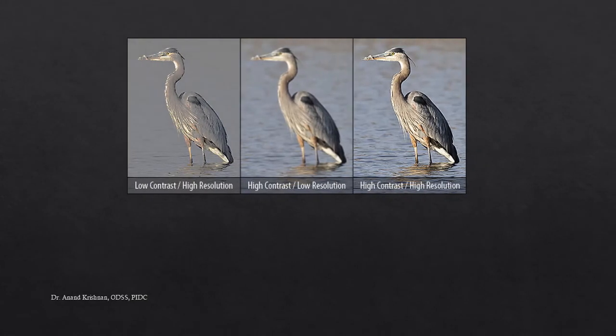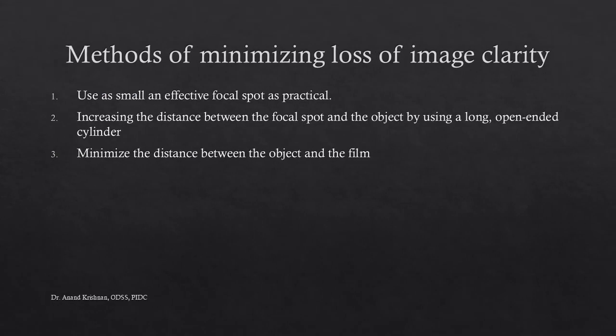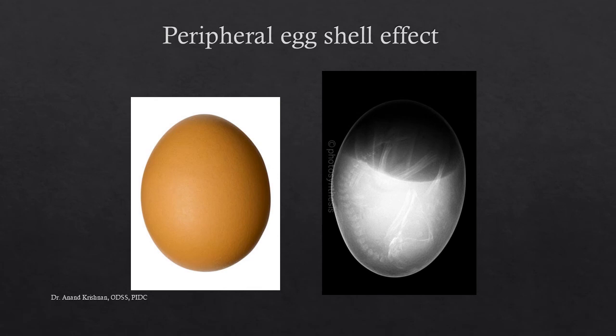To achieve good image quality, contrast and resolution must be balanced — high contrast with low resolution or high resolution with low contrast are not ideal. Methods to minimize loss of image clarity include using the smallest effective focal spot practical, increasing the distance between the focal spot and the object using a long open-ended cylinder, and minimizing the distance between the object and the film.